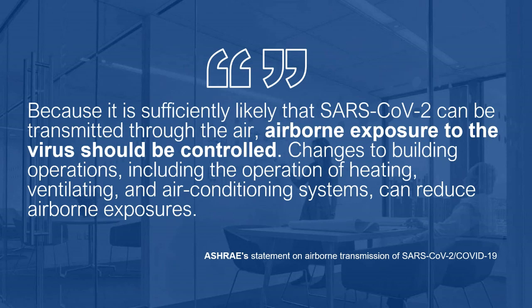We just received a report last Sunday from Oregon Health Sciences University, where they measured COVID at three air handling units in a hospital that had 80% outside air. 25% of the samples were positive, including downstream of the high efficiency MERV 15 filter.